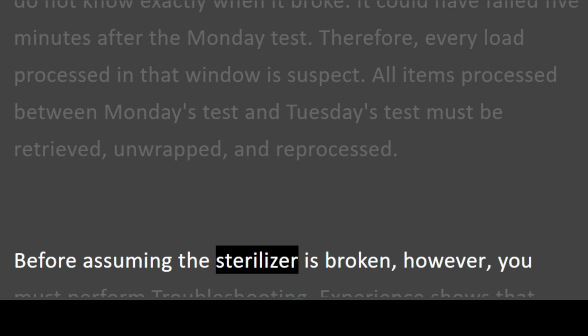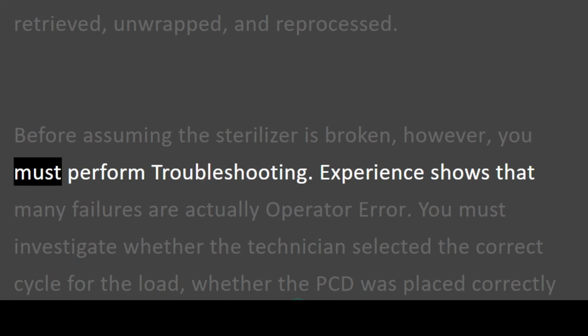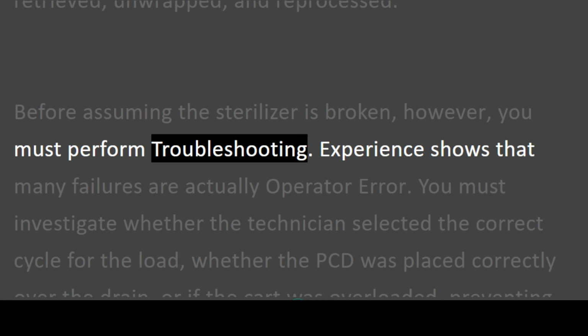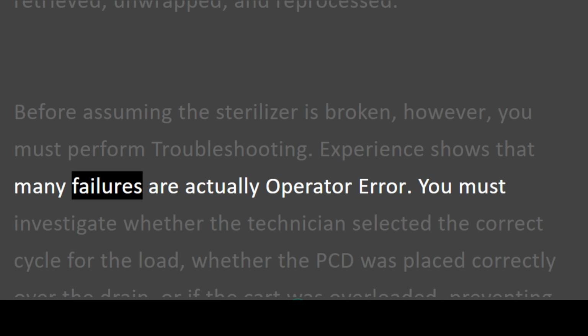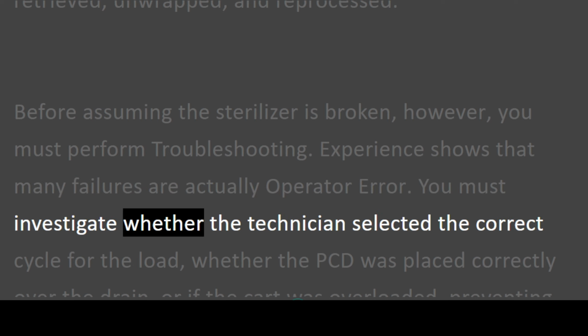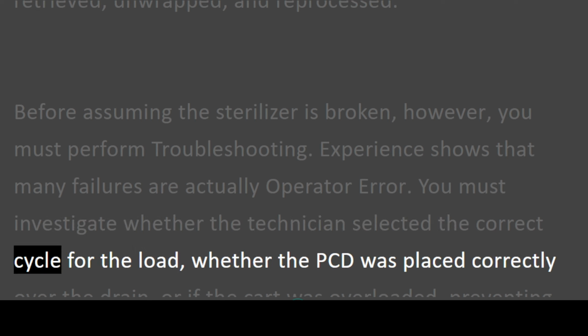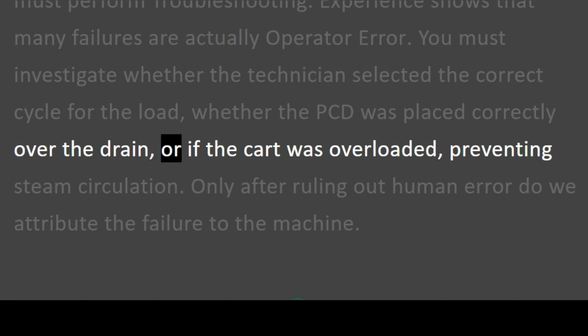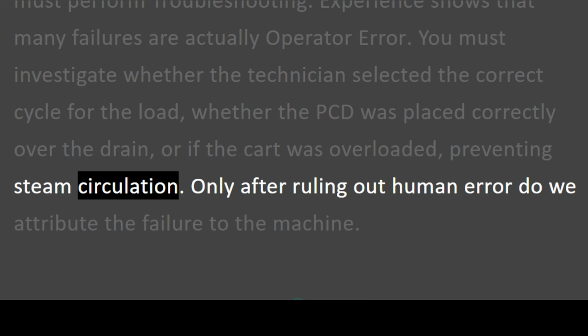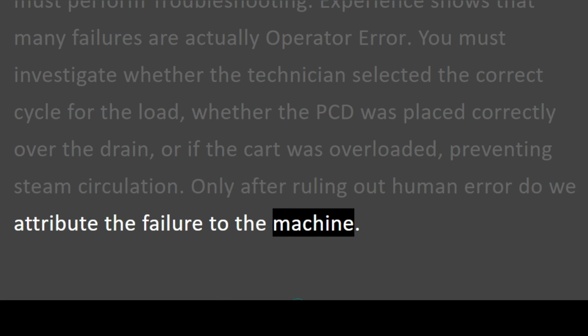Before assuming the sterilizer is broken, however, you must perform troubleshooting. Experience shows that many failures are actually operator error. You must investigate whether the technician selected the correct cycle for the load, whether the PCD was placed correctly over the drain, or if the cart was overloaded, preventing steam circulation. Only after ruling out human error do we attribute the failure to the machine.